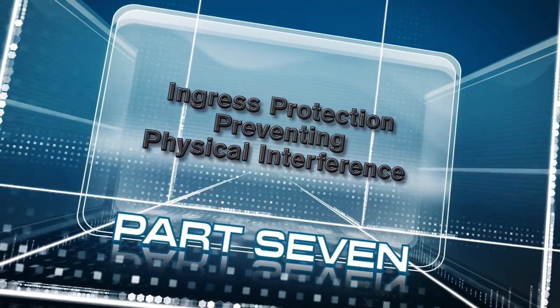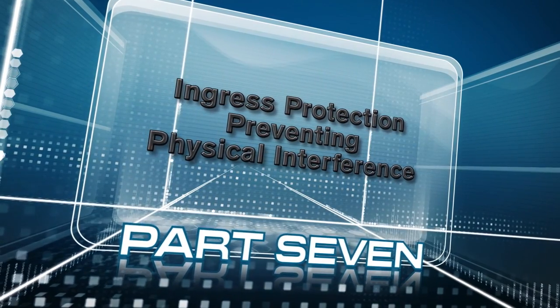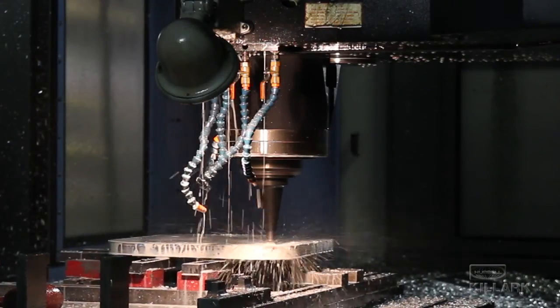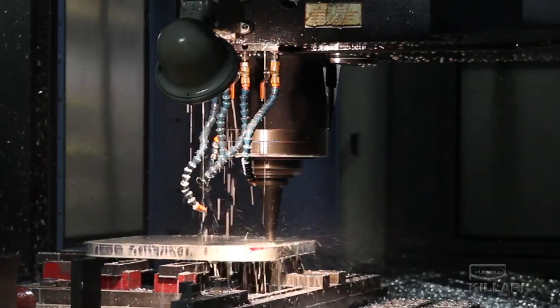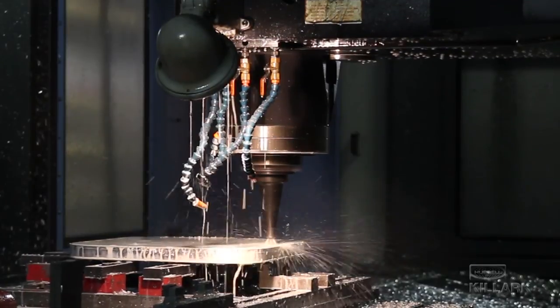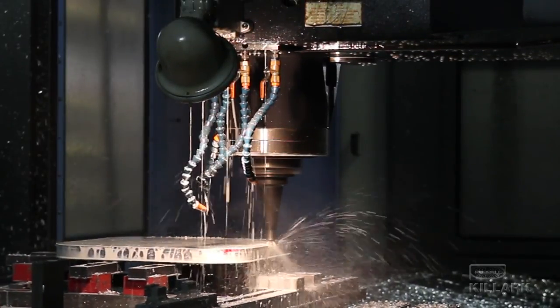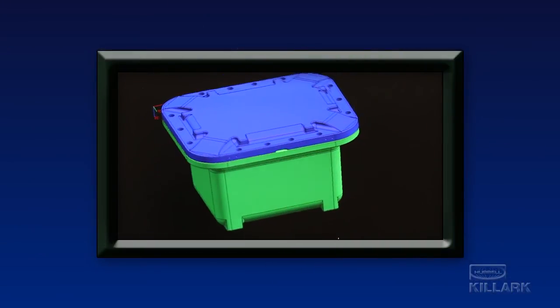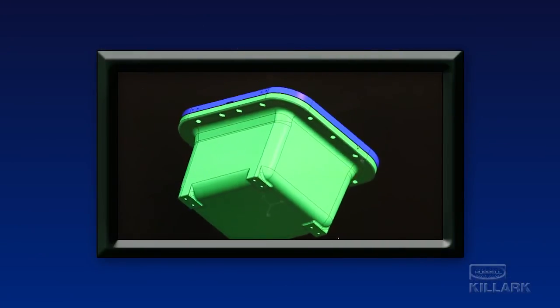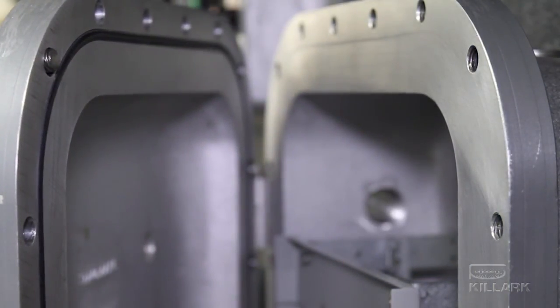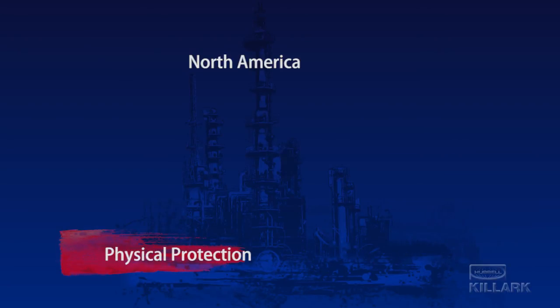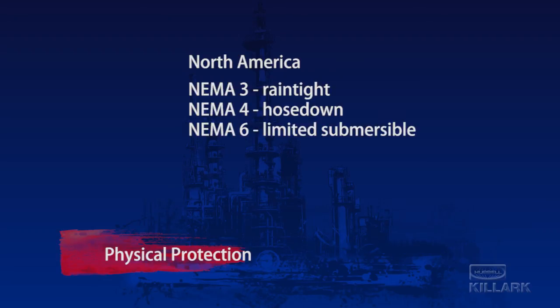Part 7. Ingress Protection, Preventing Physical Interference. The need to pay particular care to construction has always been integral to the design of explosion-proof and flame-proof enclosures. But many of the alternative protection types also depend on the design and integrity of the housing to prevent physical interference or the entrance of water or foreign matter that could defeat the equipment or component protection. In North America, designations such as NEMA 3 for rain-tight, NEMA 4 for hose-down, and NEMA 6 for submersible are typical of the environmental and physical protection ratings used for enclosures.